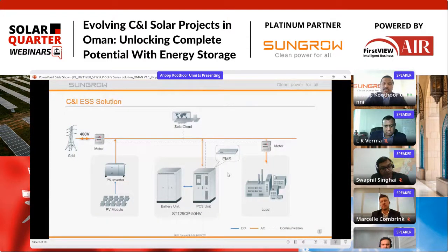So this is the C&I ESS Solutions SLD. You can see the product is available in 400 volt grid couplings. The left hand side is the PV inverters and PV modules, which are the Sungrow CX series inverters, available at 400 volt output at grid connection points. The ST129CP50HV comes with a battery and PCS, both in two different cabinets, and together we call the product ST129CP50HV. You can connect the load into that common grid point.